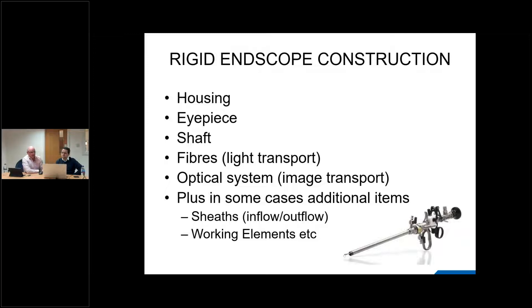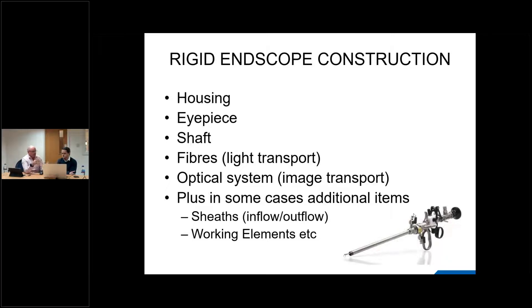Additional items make up a complete scope system. A resectoscope, for example, is made up of a telescope, a working element with a loop electrode, and two sheaths — an inflow sheath and an outflow sheath — that provide fluid for visualization. It's a bit of a misnomer when you say 'endoscope' — some people term it a telescope, some term it the total assembly — so it's slightly complicated from a terminology perspective.